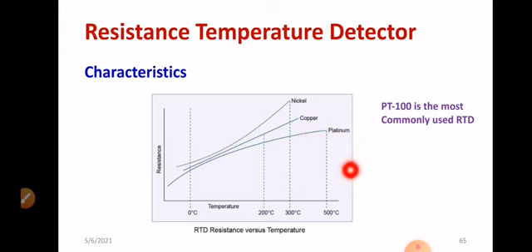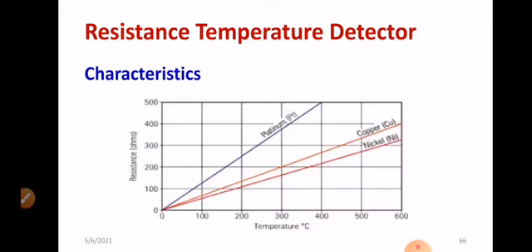Okay. For example, at 500 degrees Celsius, you are able to measure the resistance. In case of copper, for example, at 300 degrees Celsius, you can directly measure the resistance. And also at 300 degrees Celsius, you can measure the corresponding resistance of the nickel. Likewise, for the corresponding temperature, there will be a standard value of resistance. You have to find it out based on the curve. Normally, PT100 is the most commonly used RTD. It's available in the market. You can check various websites. You will be getting the information about Platinum 100, and you can also download the data sheet too. You will get different ranges. What about the temperature range? Everything you will be getting very clearly.